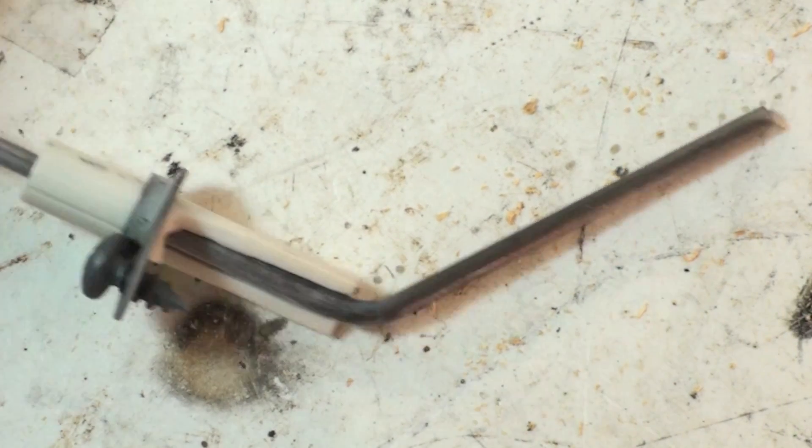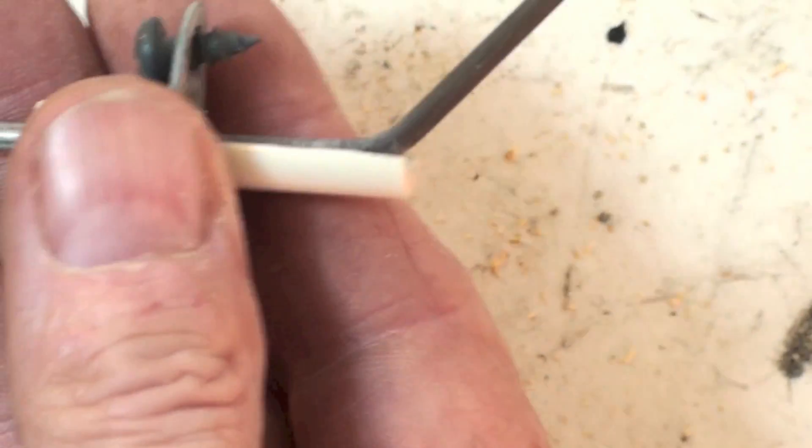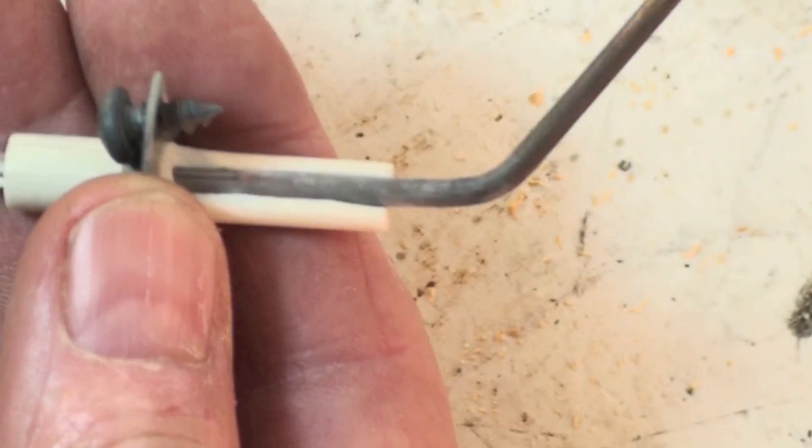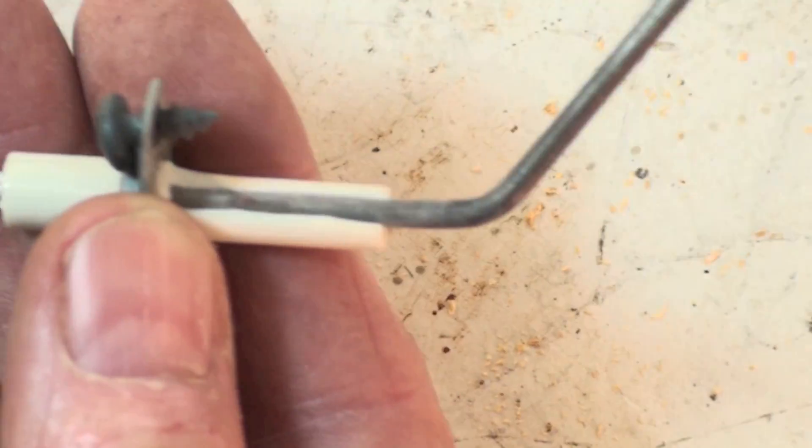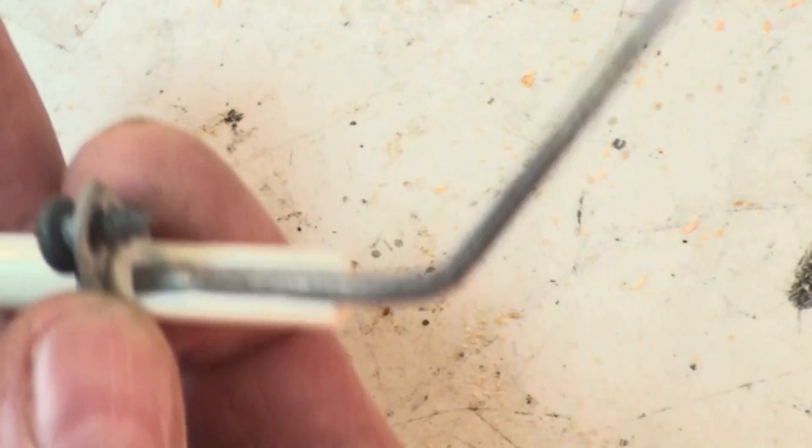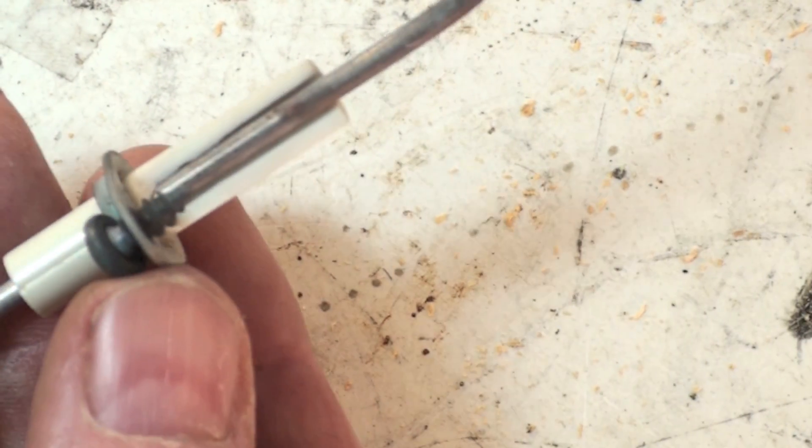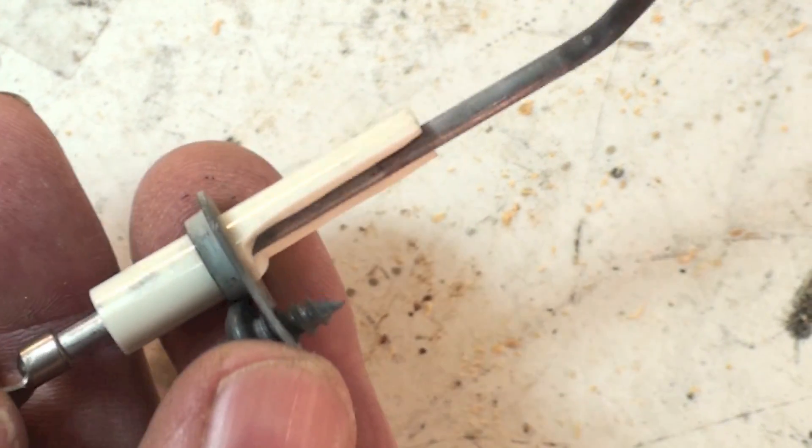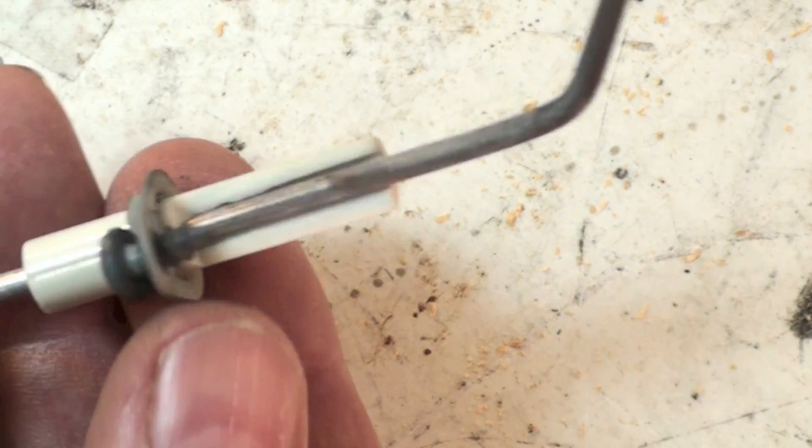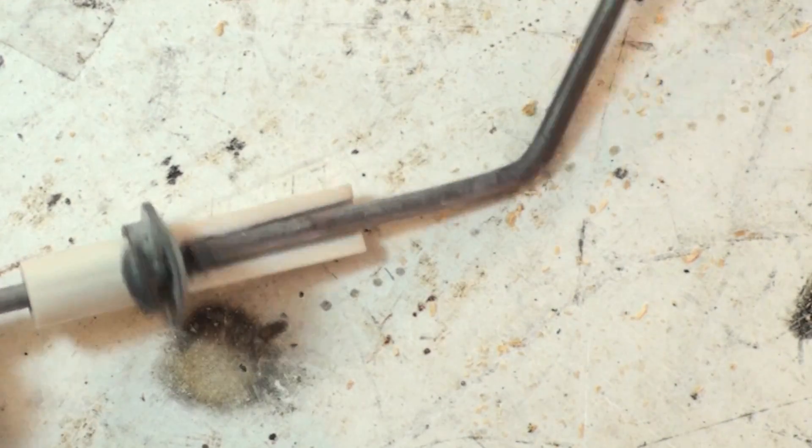Also, flame rods can end up like this where the ceramic is broken. This one actually did work, but it's not going to work long. It just rotates all over the place. So if you have cracked ceramic on these things, certainly you're going to have to replace the flame rod.